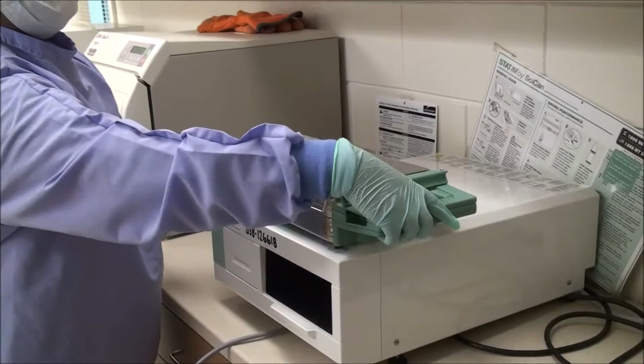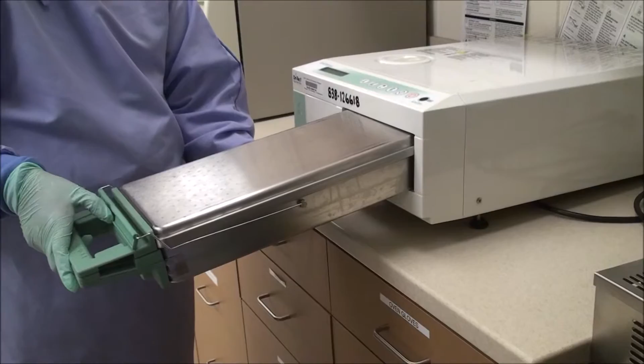Hold the cassette handle in one hand and carry handle in the other. Place the end of the cassette into the unit and drop the carry handle into the closed position. Gently push the cassette until you hear a click. Check water reservoir for adequate level of distilled water. Select the appropriate cycle, wrapped or unwrapped. Press start. The sterilizing cycle ends when the reminder tone sounds, the amber light flashes, and the message "Cycle complete" is displayed.